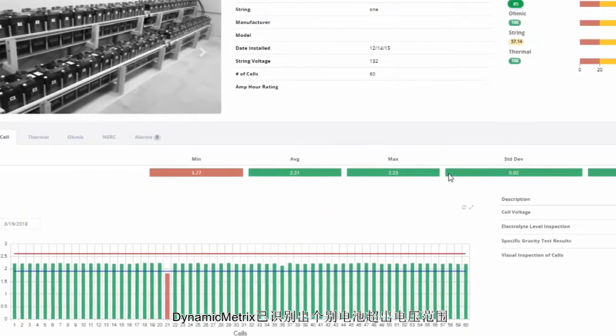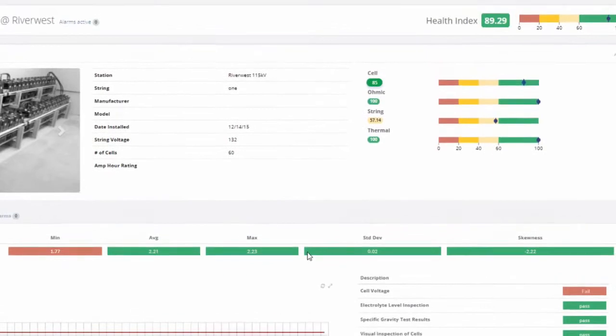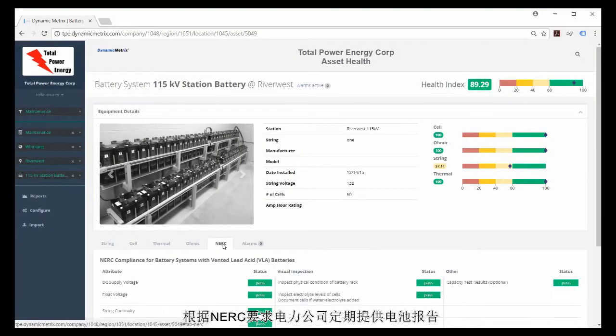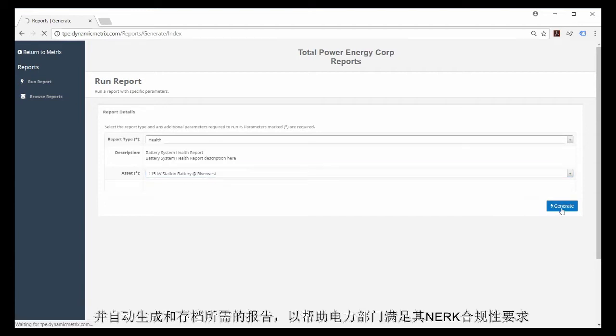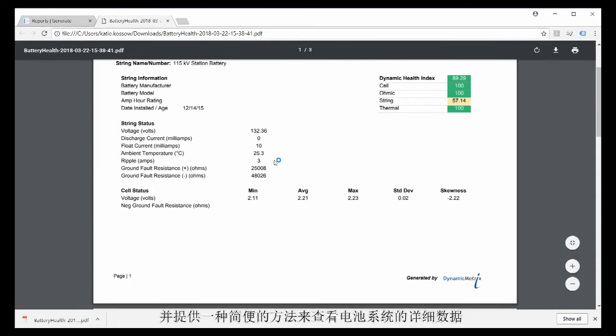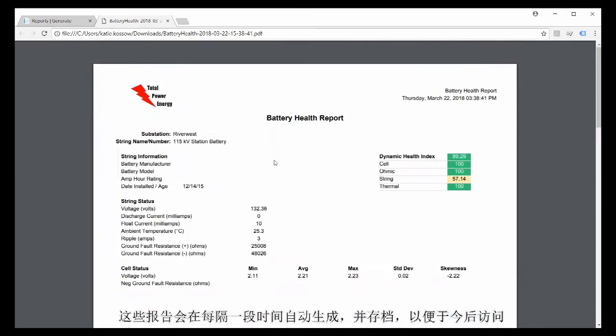DynamicMetrix shows the current state of these parameters in an easy-to-see trend chart and allows trending over time to see where changes are occurring. Here is an example of an unhealthy battery: DynamicMetrix has identified a single battery cell with voltage outside the acceptable range and has adjusted the battery string's health index accordingly — now they know they need to address the problem with cell 21 on their next site visit. DynamicMetrix can incorporate offline or online inspection data and automatically produce and archive NERC-required reports, with PDF files stored on a file share for easy access.